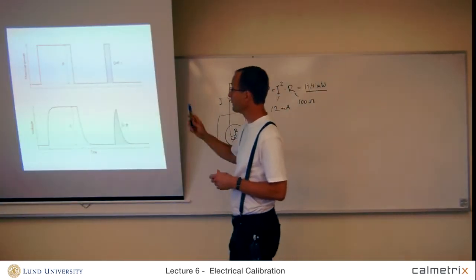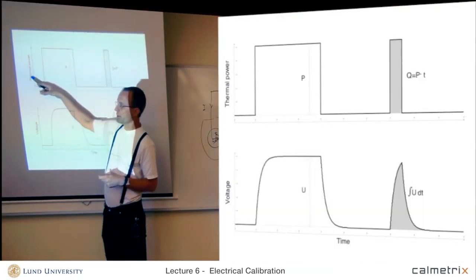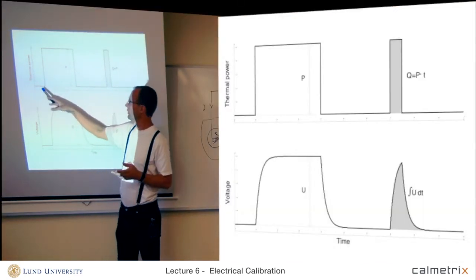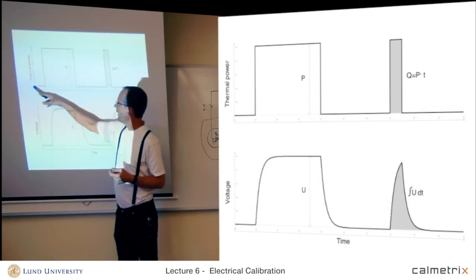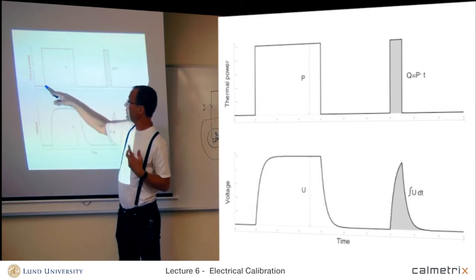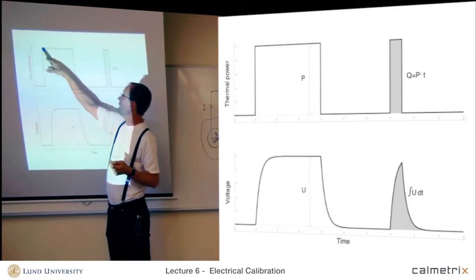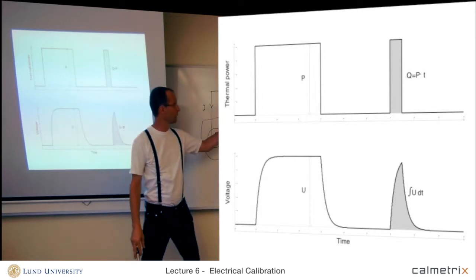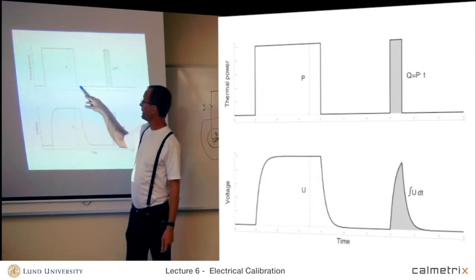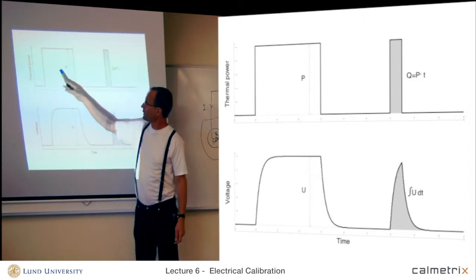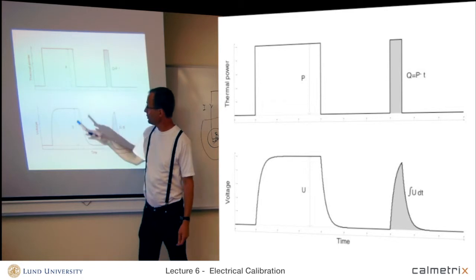And if you look here, we can see the result of this. This is the thermal power input from the electric calibration. And here we have a baseline. Here we turn the heater on, turn the voltage on. And here we have a constant, in this case, 14.4 milliwatt. And here we turn it off and go back again. So, we have a certain thermal power being produced.